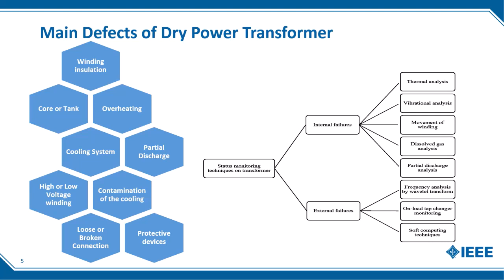Thermal overheating occurs when the transformer's temperature exceeds its safe operating limits, caused by various factors such as overloading. Partial discharges are localized electrical discharges that only partially bridge the insulation between conductors. These discharges can deteriorate transformer insulation and lead to breakdowns. Identifying and understanding these defects is essential for effective predictive maintenance.